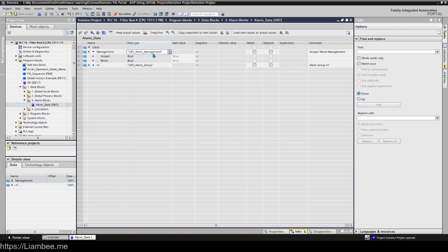If you did this in your own systems, you could create a mute button or a mute and a clear button, depending on how you're managing your alarms. Some people will be happy with just an accept and reset and they self-clear, and on accept, you automatically mute any audible warnings. Some people will want to mute separately. They'll want to be able to accept, reset, and clear alarms all individually. Obviously, all those settings are dependent upon your HMI or SCADA and how you're managing your alarms.